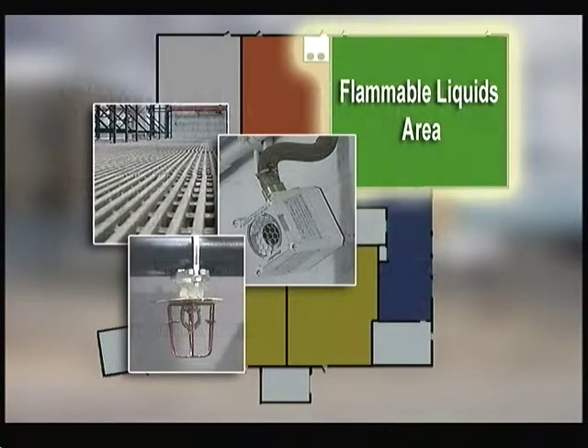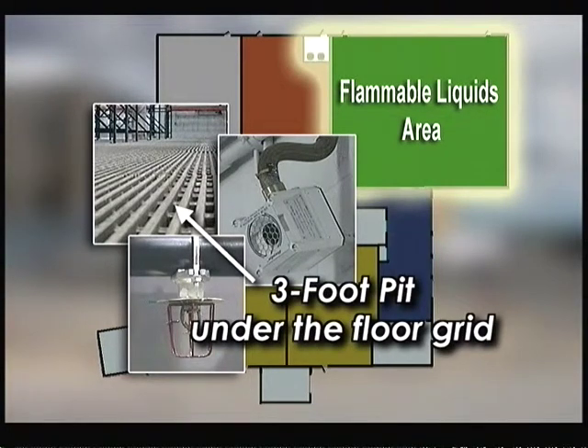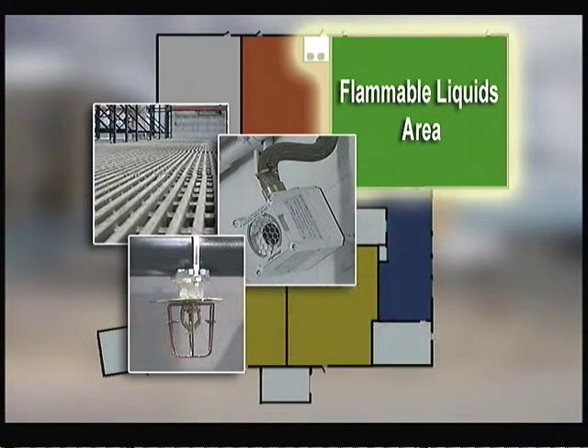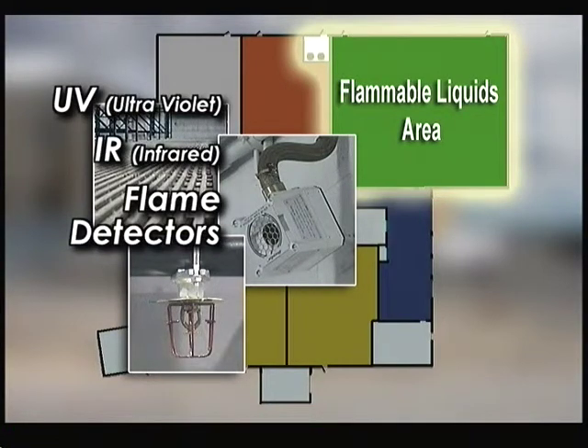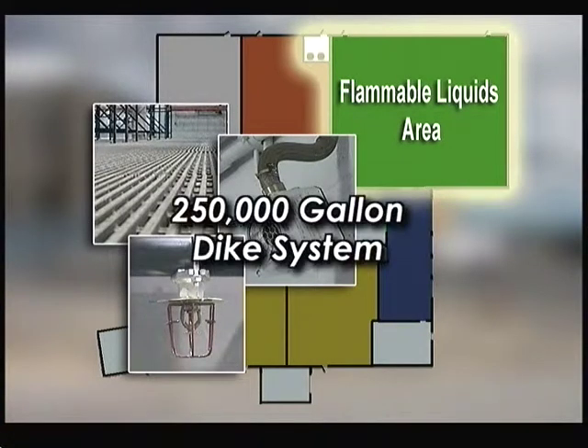The flammable liquids and solids are each in explosion-proof environments with chemical-resistant materials on the floors and walls. The flammable liquids room has a 3-foot pit under an epoxy-coated steel grid and FRP floor system. The suppression system is an AFFF foam system. UV, IR, and flame detectors act as an early warning in case of an incident. The building is completely diked, housing a possible 250,000 gallons of liquid.